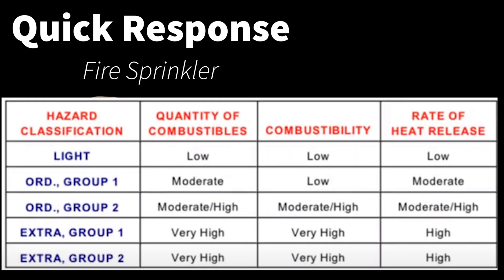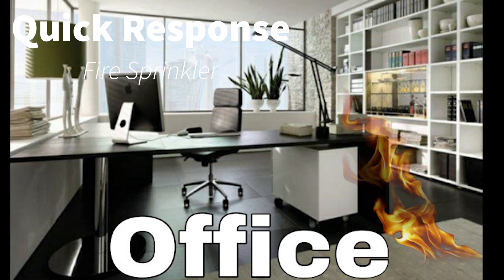Now let's look at how the different response times are applied, starting with the quick response. On this chart you will see the hazard classifications on the left. Light hazard occupancy shows low combustible loads and rate of heat release. All light hazard occupancies will use quick response fire sprinklers — the earlier the water is applied, the faster the fire is controlled with the operation of fewer sprinklers. Examples of light hazard occupancies are an office and a school.